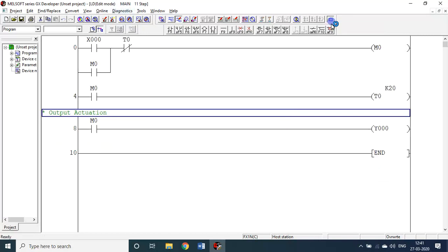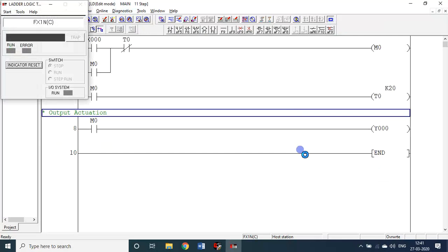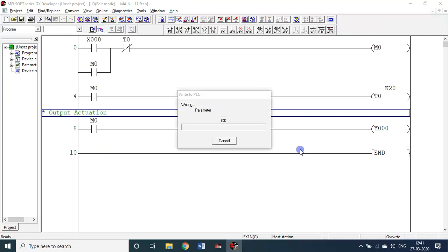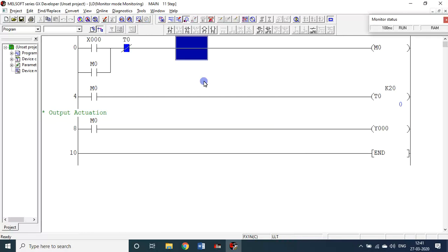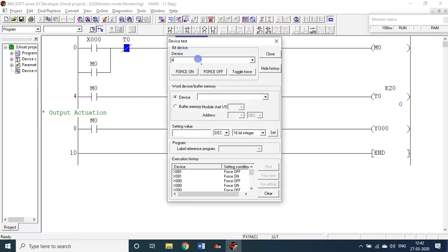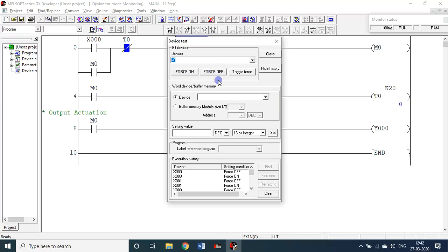Shall we see that? Go for device test. Alt+F1 device test. X0: I will force on for a fraction of a second then switch off. You see the timer T0 starts counting — the number goes from 0, 1, 2, 3, 4, 5, 6... up to 20. When it reaches 20 it becomes on. If it is on, this will cut M0 — M0 is cut, Y0 is cut. Until then M0 and Y0 are on.